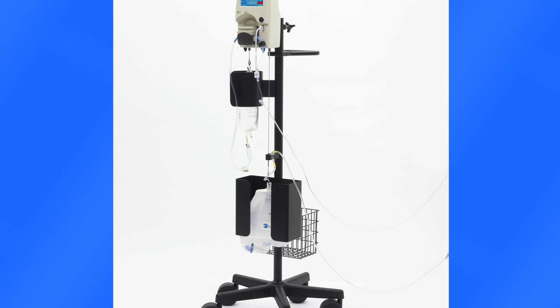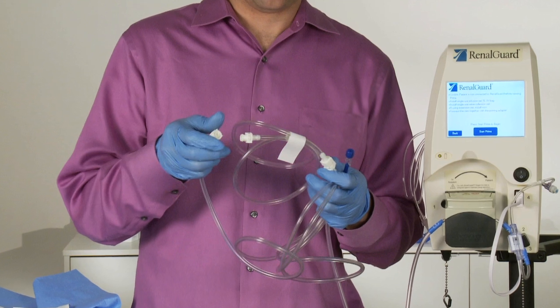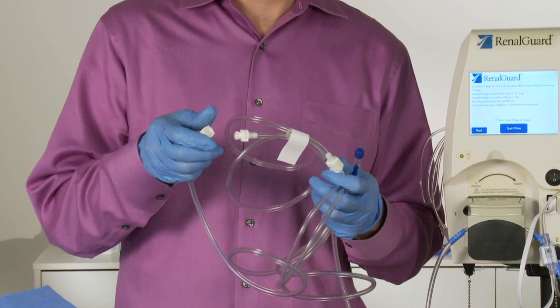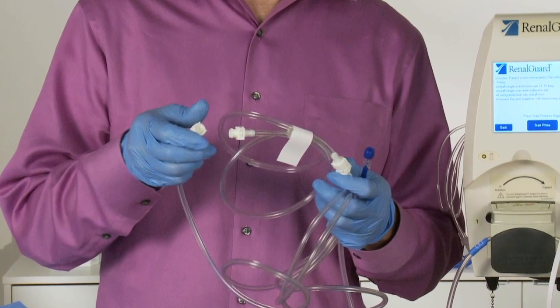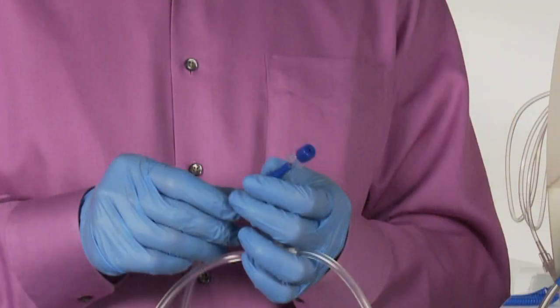The urine collection set is made up of a urine collection bag, narrow tubing, and a Foley adapter with integrated sampling port. You'll notice that the urine line is much longer than a standard urine collection bag to allow RenalGuard to be placed at a good distance from the patient when space is at a premium, such as in a cath lab. If the tubing is not long enough, each single-use set also includes an extension set to give you 3 more feet of tubing. The urine collection set comes packaged with a blue priming adapter that is used for priming. We will review that in a moment.